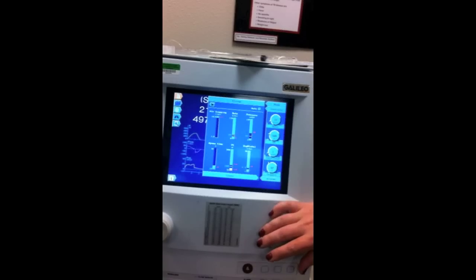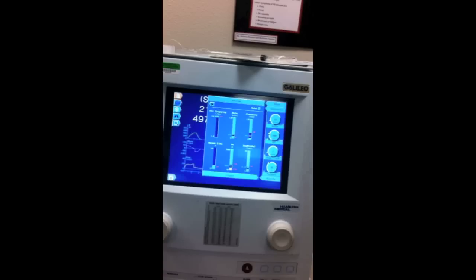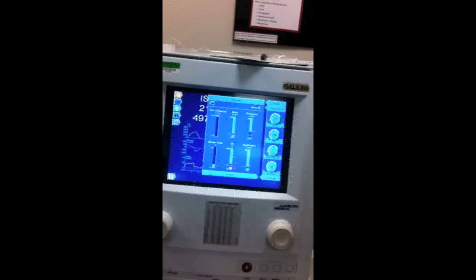And tomorrow we'll talk about alarms, but tidal volume 200 below, 200 above. Rate is going to be 10 above the average respiratory rate. Pressure, high pressure 10 above, but no more than 35. So if your high pressure is 20, you'd set your high pressure alarm at 30, 10 above the average. Remember that these are not going to be set the same every single breath. But if your pressure is averaging 30, you would go to 35. So we go 10 above, but no more than 35.